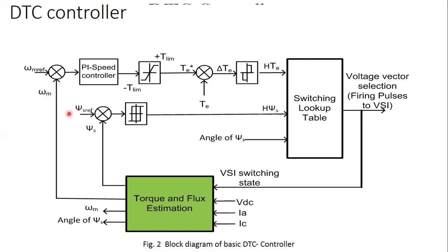The second loop is for flux. In an induction motor we keep flux constant, so the flux reference is compared with actual flux and the error is given to a two-level flux controller, outputting +1 to increase stator flux and -1 to reduce it. Additionally, the angle of the stator flux is required — its position in the 0–360 degree plane. Based on these three pieces of information, a switching lookup table selects an appropriate voltage vector, providing firing pulses to the VSI, which produces the required voltage and frequency for the induction motor.